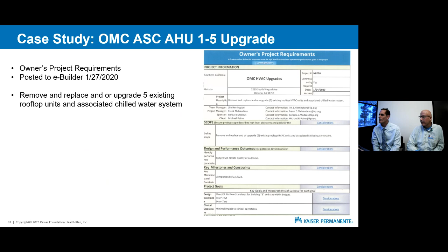The basis of design addressed the need to lower the temperatures in the operating rooms, and to do this meant a standalone chiller had to be added so that you could lower the discharge temperature of the air handling units. The BOD did not have energy considerations, and also didn't address fan power, day-night scheduling, night setbacks, or any turndowns at the zone level. We didn't do anything at the zone level. We only looked at stuff above the roof.